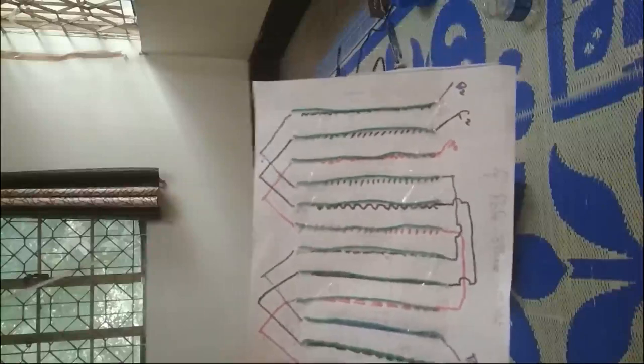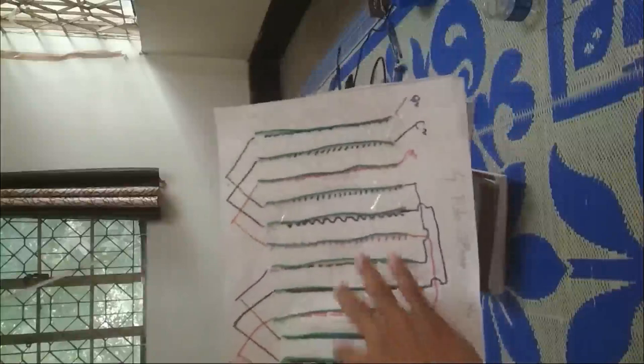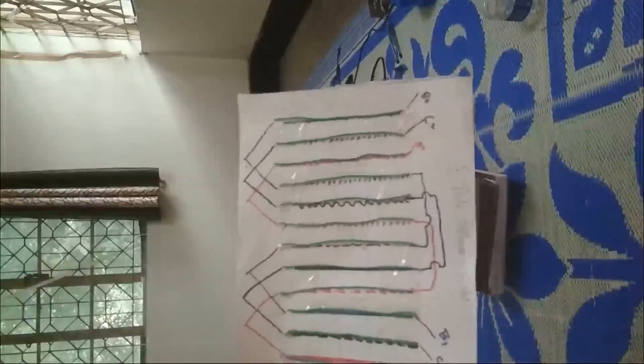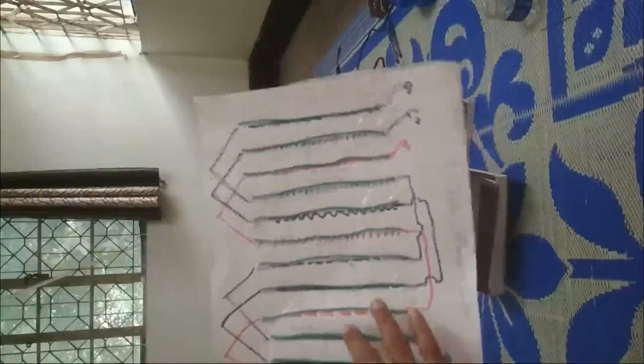Series connection is quite easy. Like a layman, you can just connect all the windings in series. Your job is done, right? But in case of parallel connection, if you think about connecting all these four slots in parallel, you will find yourself in a very pathetic situation, because your machine will be burnt out. Because if you short all the conductors in parallel, then basically you are connecting two voltage sources, like two batteries connected positive to negative. So they will form a huge circulating current that is not desirable.